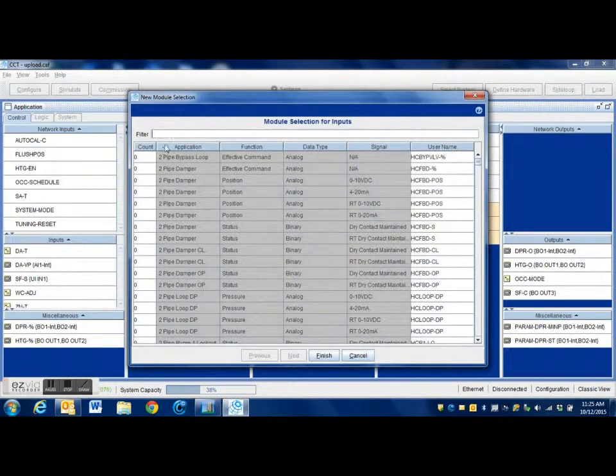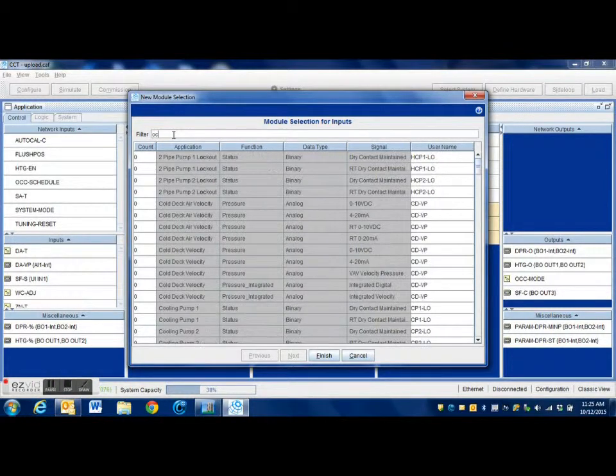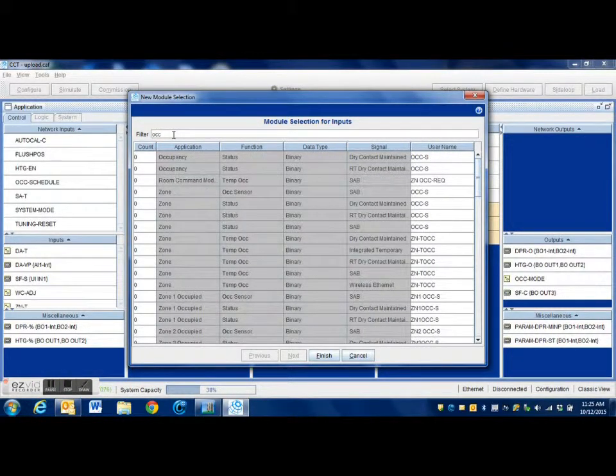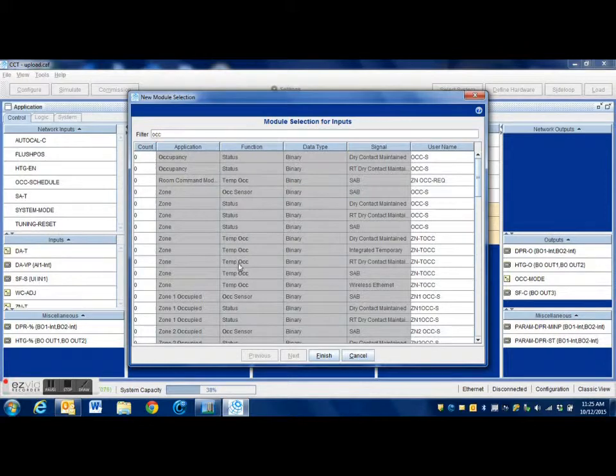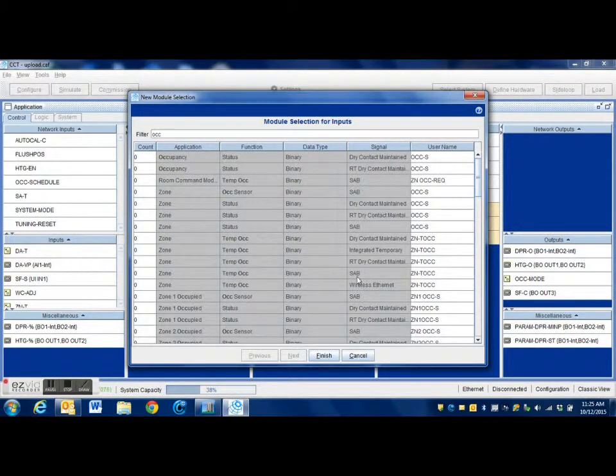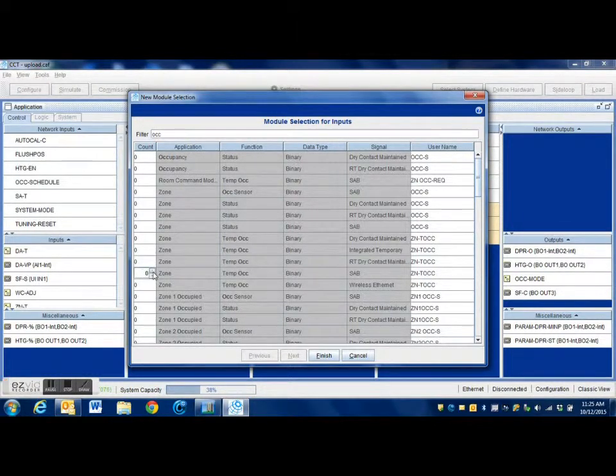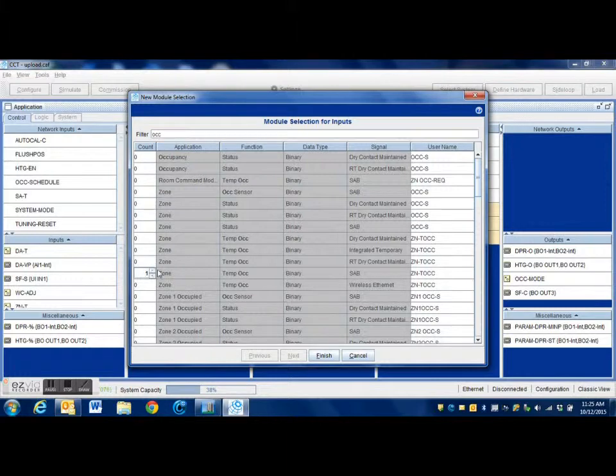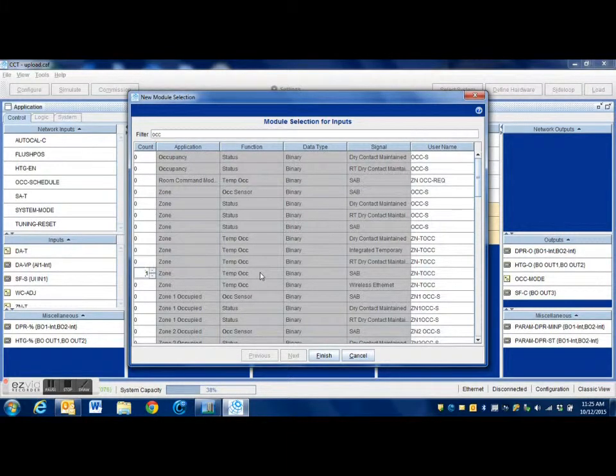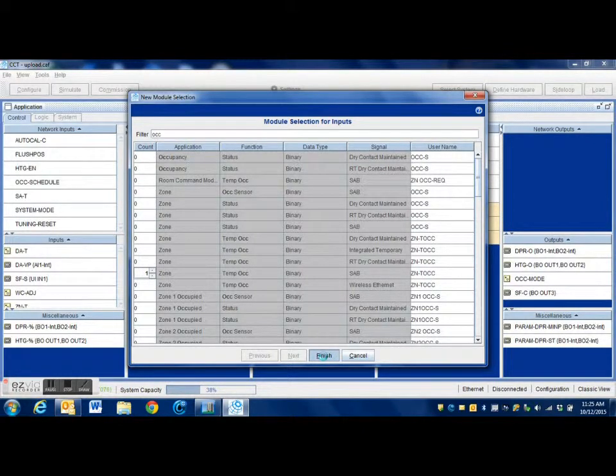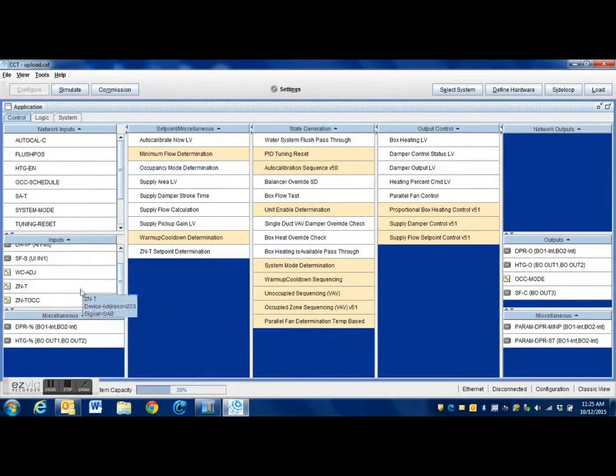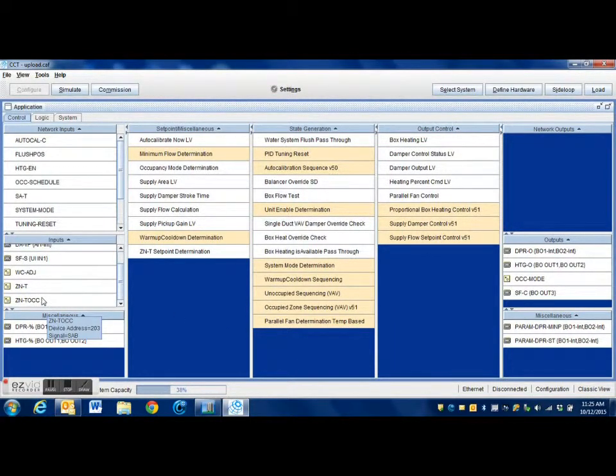We're going to use our filter and simply type in OCC for occupancy. Since these thermostats are a network sensor, we have quite a few options here. We want to select the one that is for the SAB network. You notice it is a temp occupancy override. Once we have one selected, we press next and it is going to add that to our system.